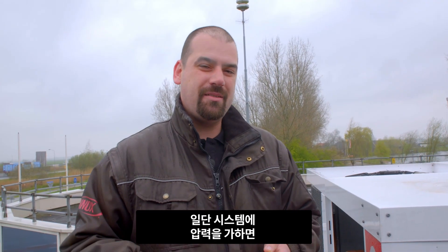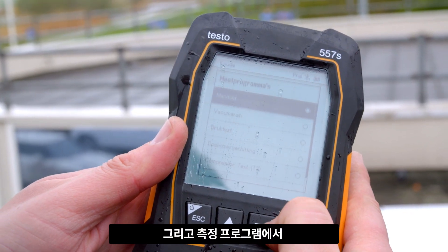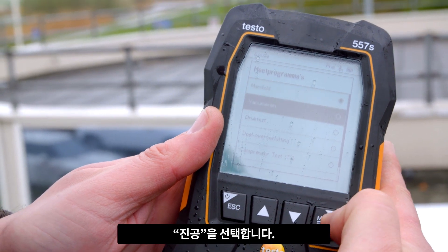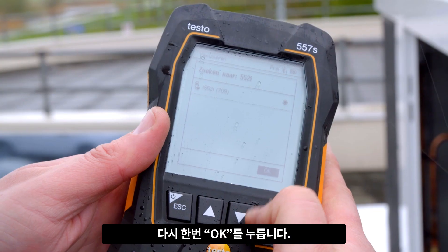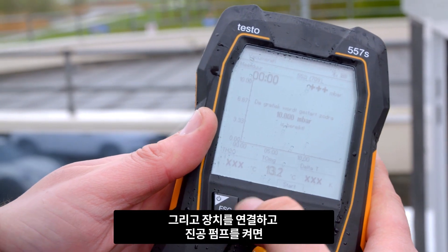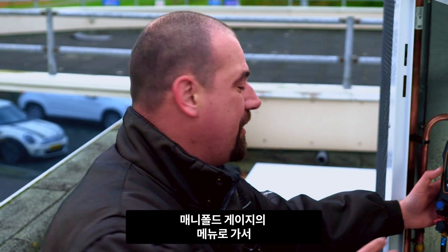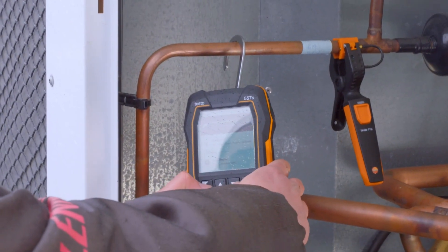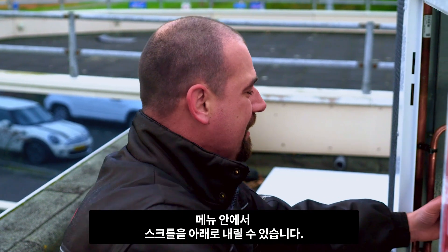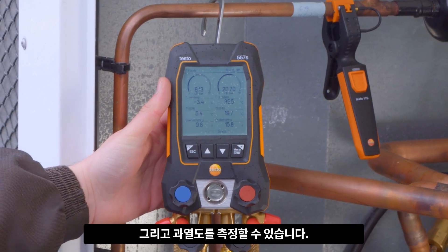Once we've put pressure on the system and that has worked well, we'll start to build up a vacuum. Then, in the measuring program, I can go to the menu and place the arrow on vacuum. The measuring instrument is recognized. After this, you connect the instrument, switch on the vacuum pump, and the measurement will start. If you go via the manifold, you can use the menu to choose the type of refrigerant to be used. Within the menu, you can simply scroll down. Here we're dealing with R410A, which we click on and then see that the instrument is also measuring subcooling and superheating.